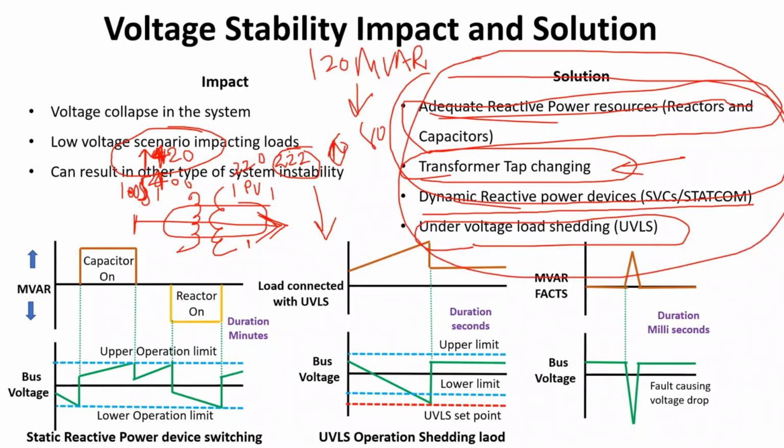And in general, the reason I always try to avoid generator point of control is that you have to think that a generator may be there and may not be there in the system. Right now, many of the generators that you were utilizing to control the reactive power are not available due to the increase of RE generation. So that is also a problem that we are facing.